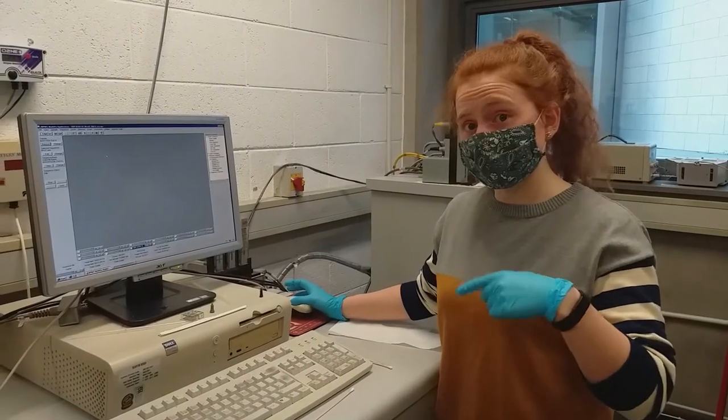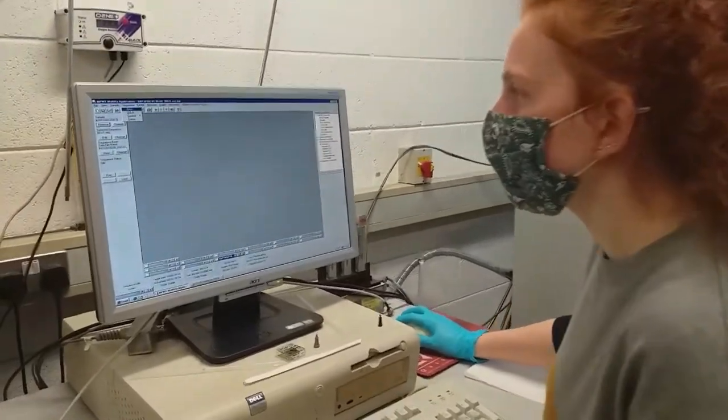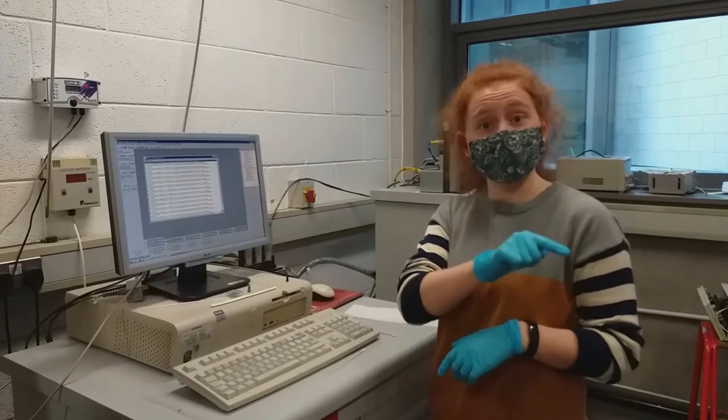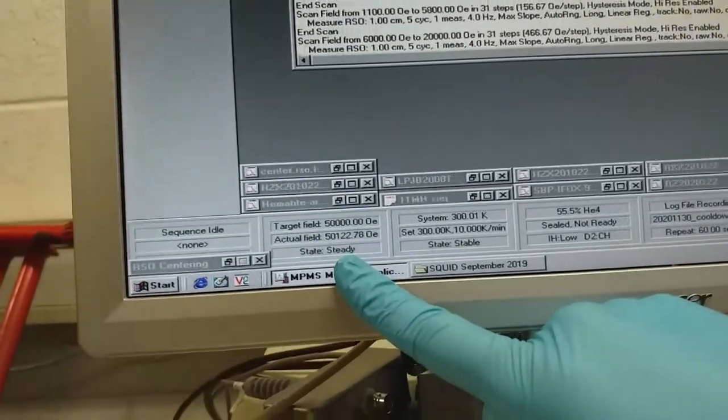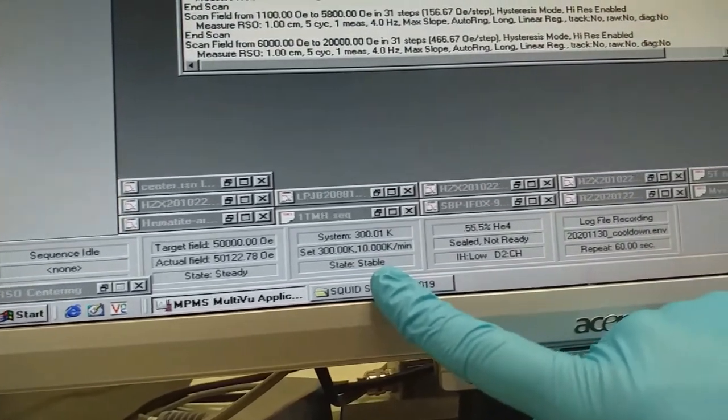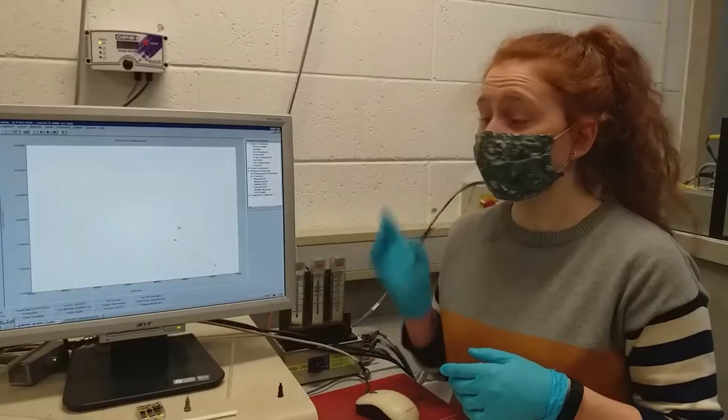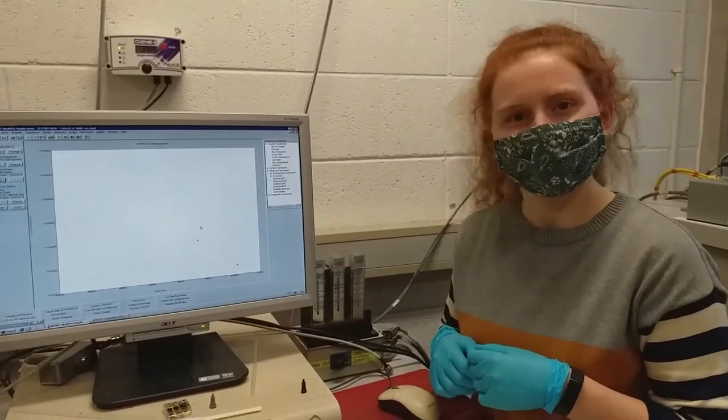Now I need to choose a sequence to run but I have one saved in my folder so I'll head to that straight away. I want to run a full loop from 5 tesla to minus 5 and then back to 5 tesla again, all at 300K. I just like to check everything once more before I actually start the measurement just to make sure everything is okay. So this is running away now, so I can come back in about 3 hours to check to see what my loop looks like.